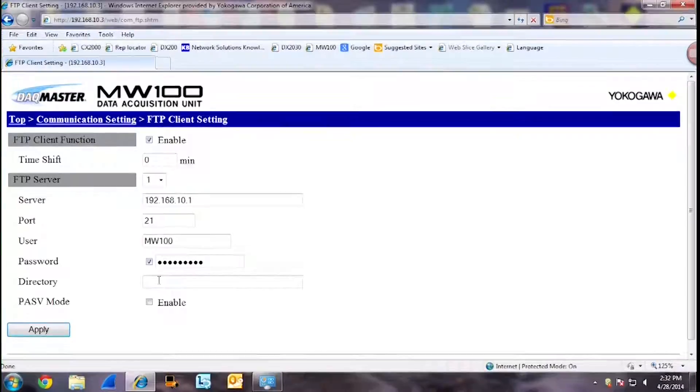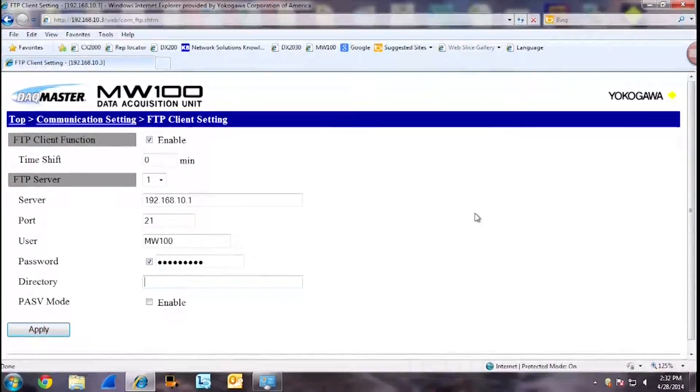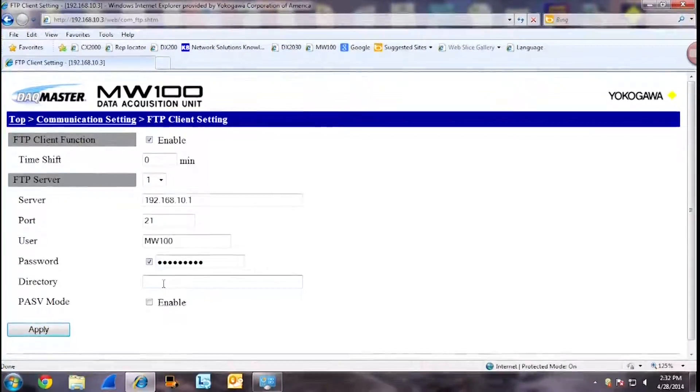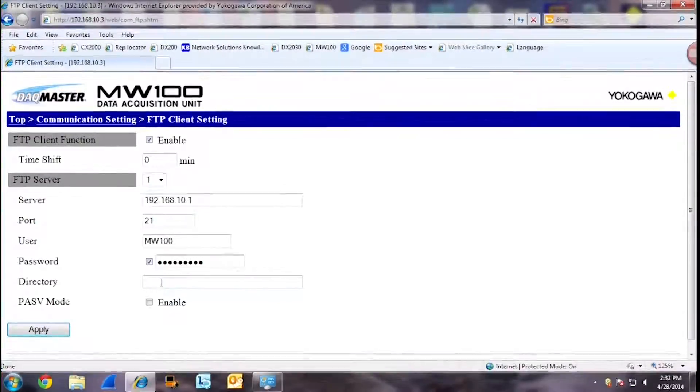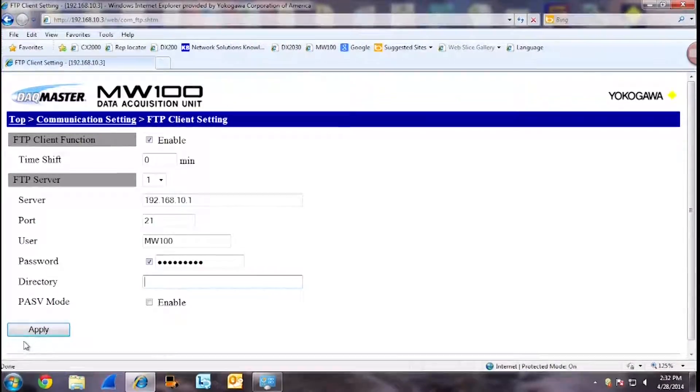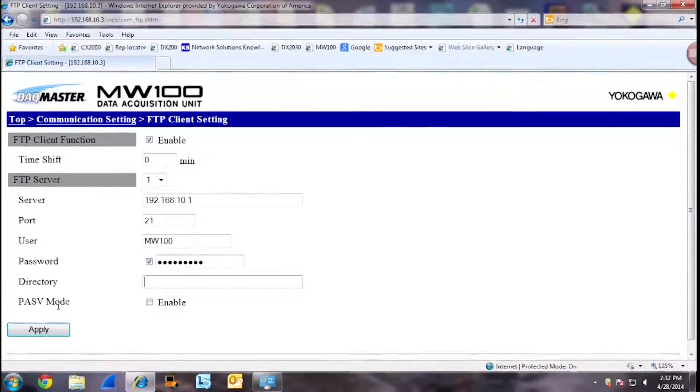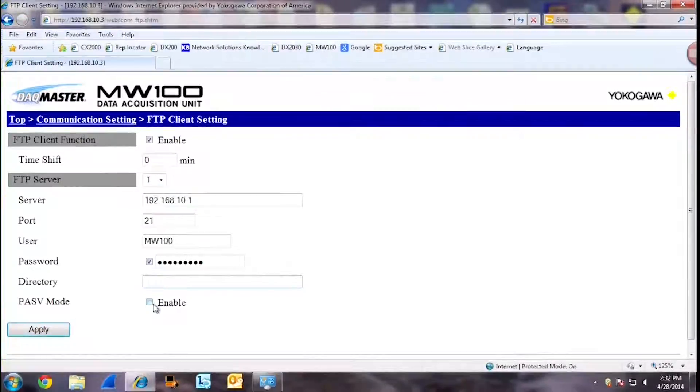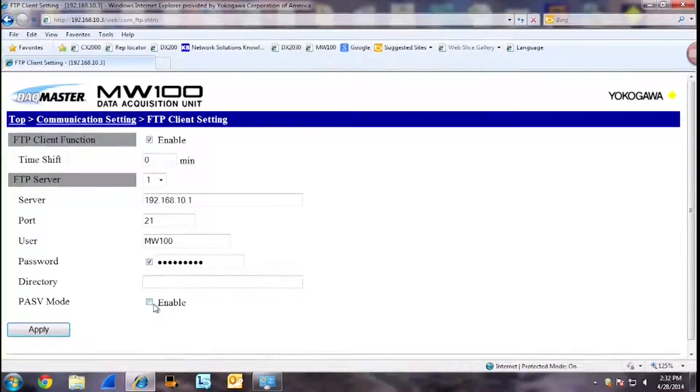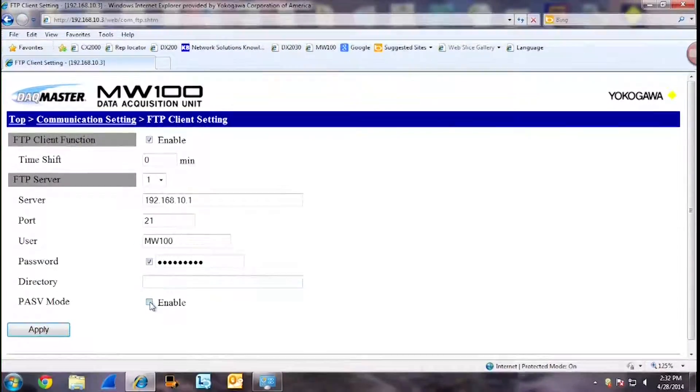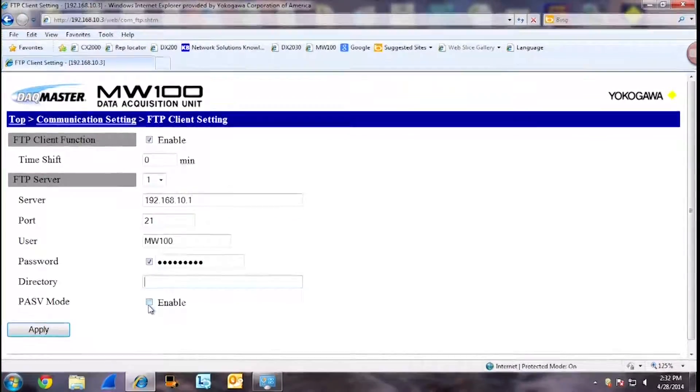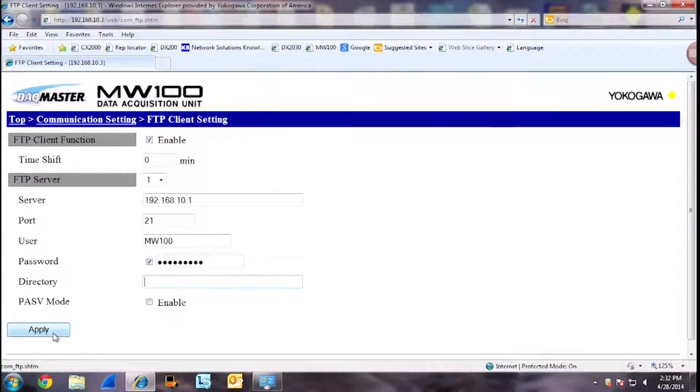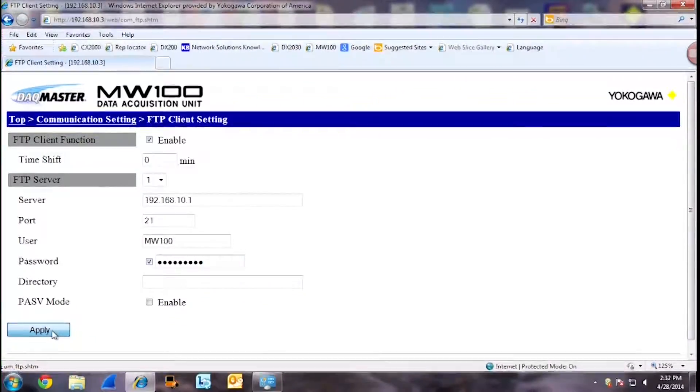The directory is the path that the data file takes to make it to the PC. If you only have one directory set up, then you can leave this blank because the FTP client will take the only path it can. PASV mode is if you are trying to transfer the data file across FTP behind a firewall. You can choose whether to enable or disable this setting. We have no firewalls running on our PC currently, so we will leave this disabled. When finished, click apply.